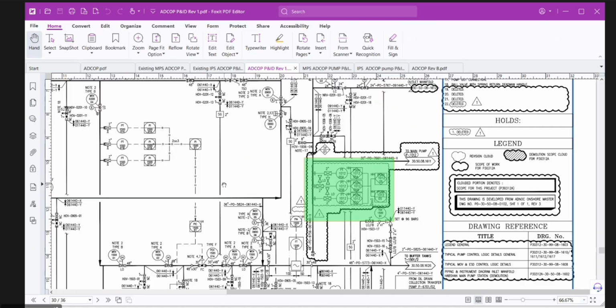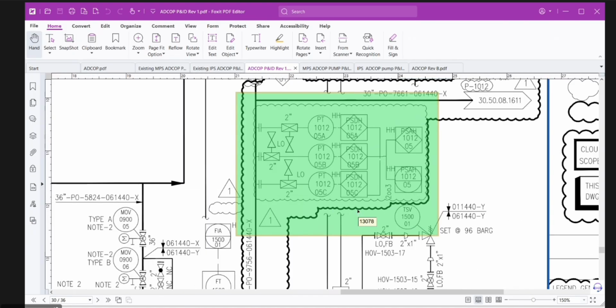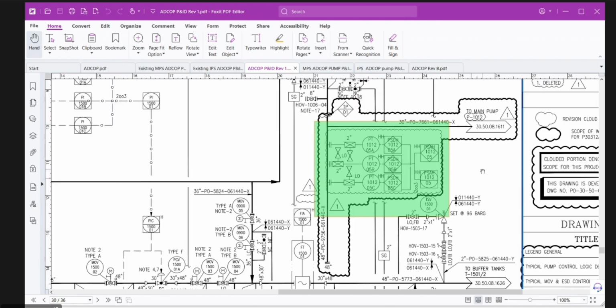No, first look at the whole picture. On the pump suction, we have added 2 out of 3 voting low pressure trip in order to avoid the scenario of shut-off pressure.